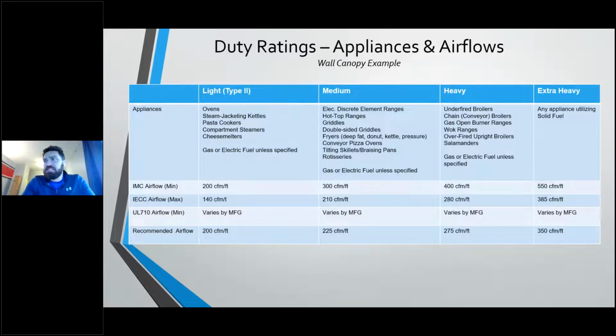And you're going to get a different answer on CFM per foot depending on what individual you talk to, whether that be in the engineering community or in the manufacturing community. It really is just based on experience and on the specific appliance lineup. So let's say I had a gas charbroiler, but it was only 2 feet wide, and it was in the middle of my appliance lineup, and this wasn't a very heavy duty restaurant. Maybe they have the charbroiler for one thing, they just don't use it a lot, right? I may at that point take that into consideration and say, well, let's save some energy. Let's go 250 CFM per foot, or even down to 240 CFM per foot, just so long as you don't go under the UL 710 airflow minimum. And again, I would almost never go to that for any one of these.